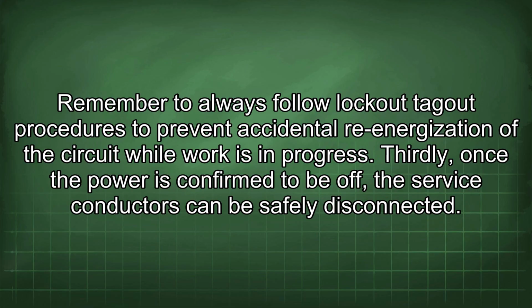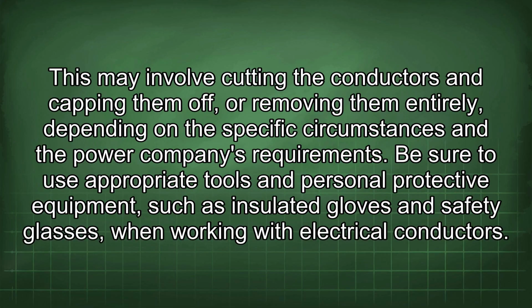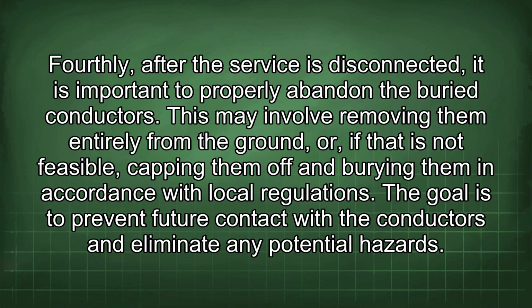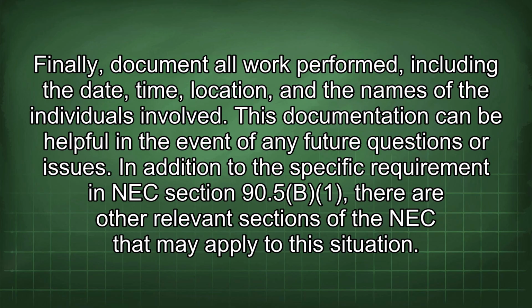Thirdly, once the power is confirmed to be off, the service conductors can be safely disconnected. This may involve cutting the conductors and capping them off, or removing them entirely, depending on the specific circumstances and the power company's requirements. Be sure to use appropriate tools and personal protective equipment such as insulated gloves and safety glasses when working with electrical conductors. Fourthly, after the service is disconnected, it is important to properly abandon the buried conductors. This may involve removing them entirely from the ground, or, if that is not feasible, capping them off and burying them in accordance with local regulations. The goal is to prevent future contact with the conductors and eliminate any potential hazards. Finally, document all work performed, including the date, time, location, and the names of the individuals involved. This documentation can be helpful in the event of any future questions or issues.